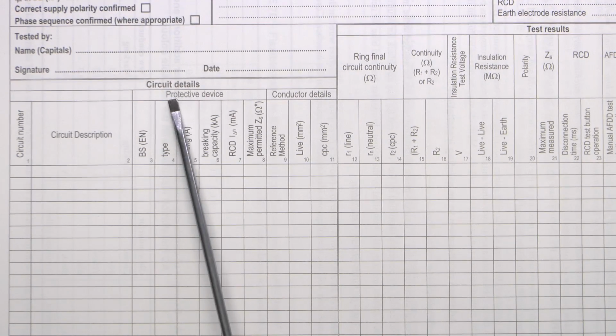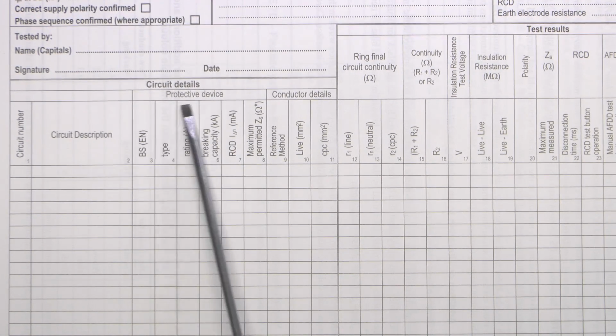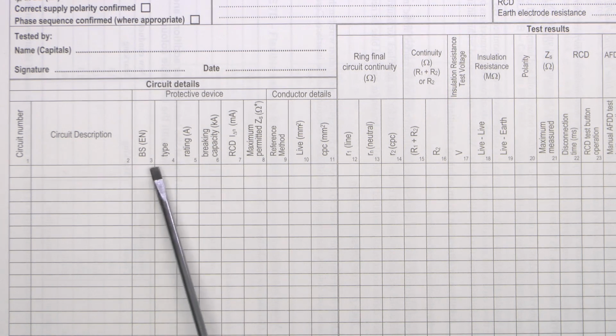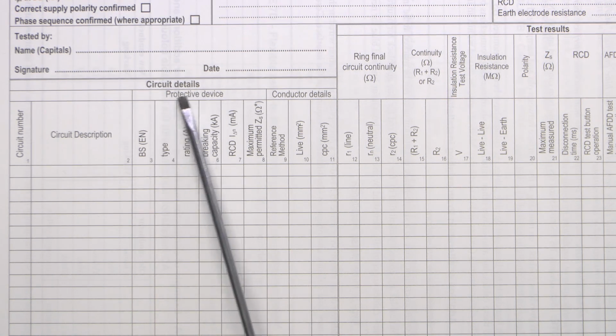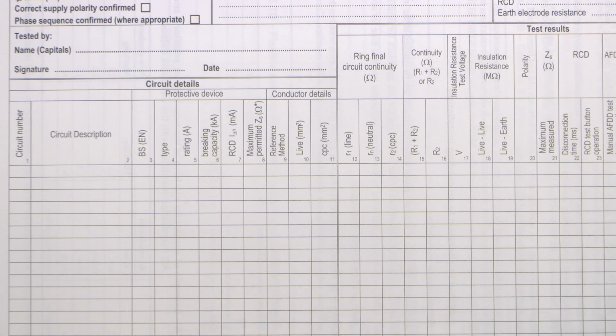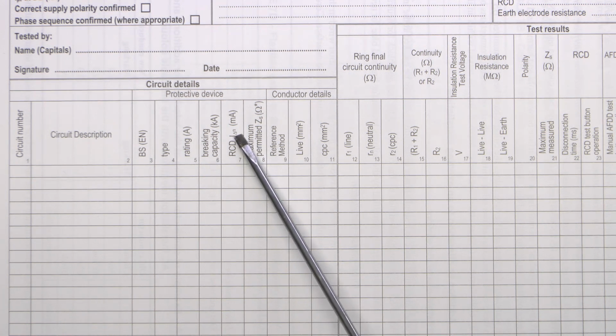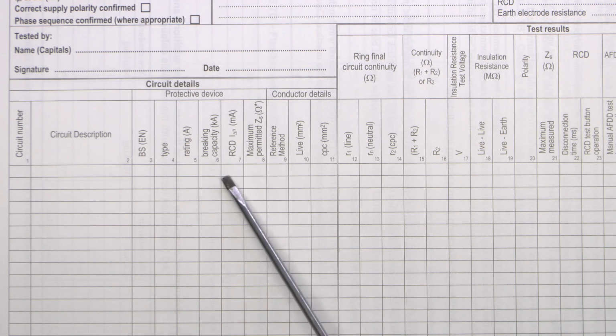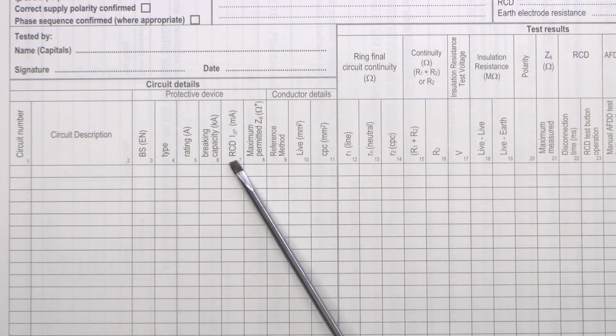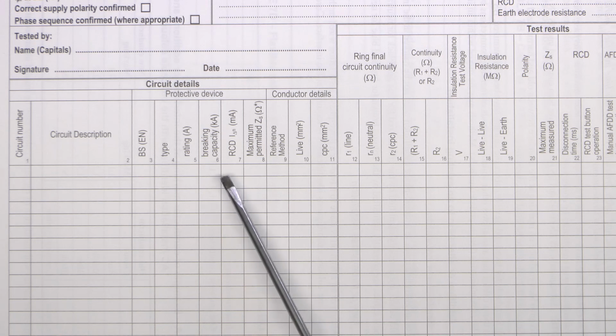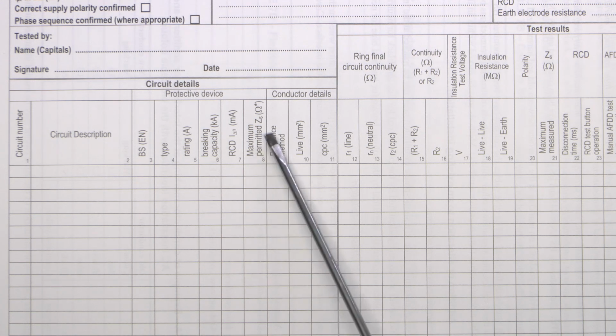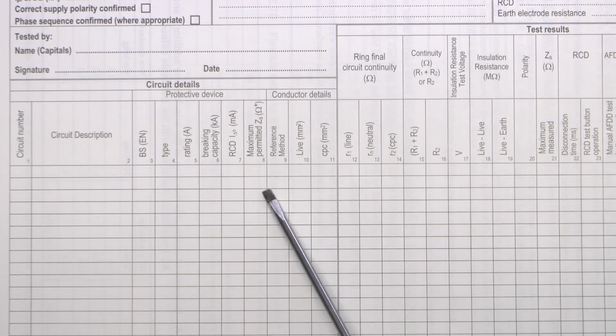We've now got in here protective device across the top of the various columns. Previously it said overcurrent device, so there's a minor wording change. In terms of the columns themselves, most of these are the same. We've got a couple of additional columns now. We've got one here for the actual RCD trip current, so that's in milliamps, so typically it will be say 30 milliamps, or other values are available, so that's now added in here. Also we have the maximum permitted loop impedance. Again, that's put in there. That was included on quite a lot of other forms anyway, it's just been added to the model here.